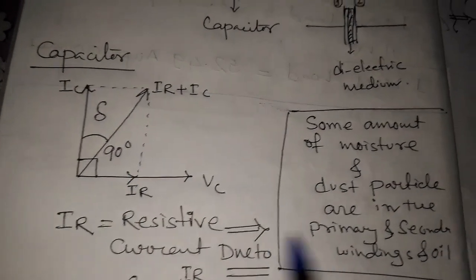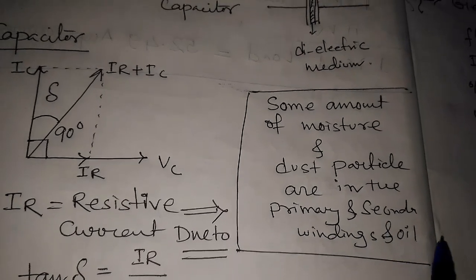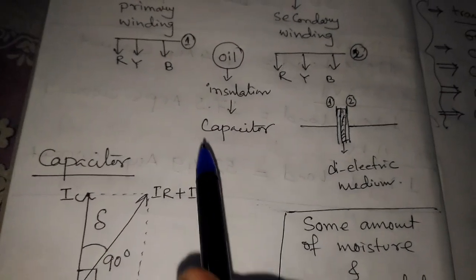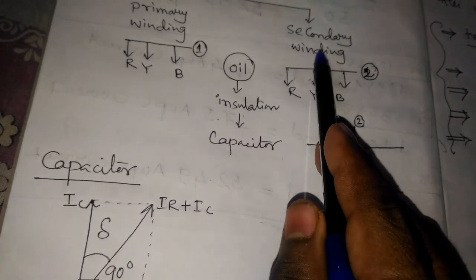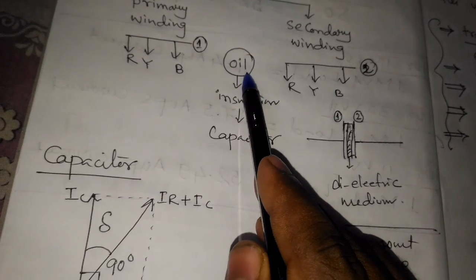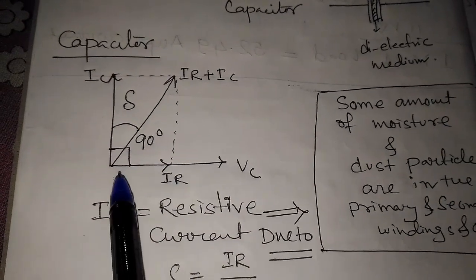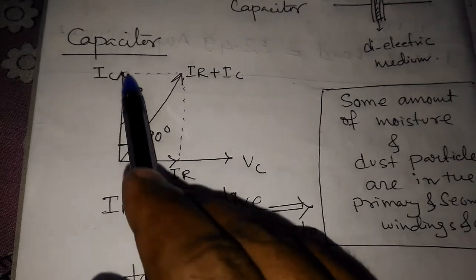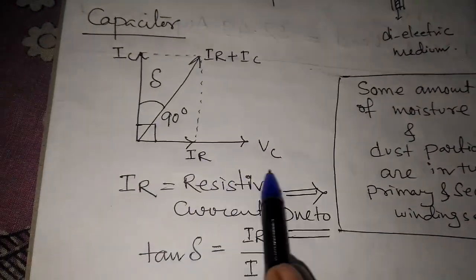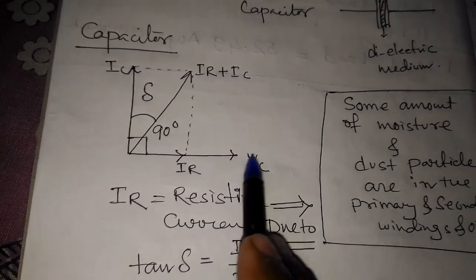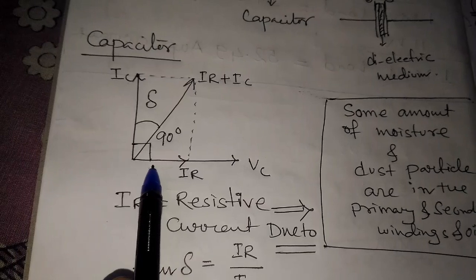If we discuss about the Tan Delta, some amount of moisture and dust particles are present in the primary and secondary winding and oil. These impurities — dust particles and moisture in the oil — deteriorate the insulation. In the phasor diagram, IC is the capacitive current and VC is the voltage applied to the capacitor. For a pure capacitor, the angle between IC and VC is 90 degrees.